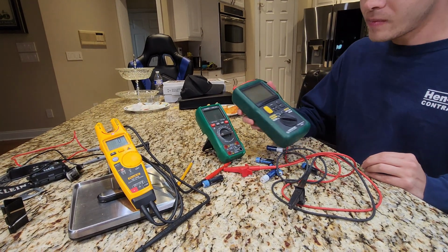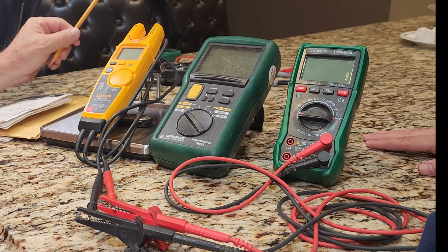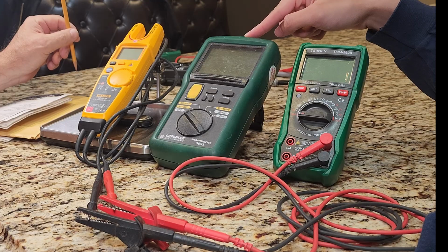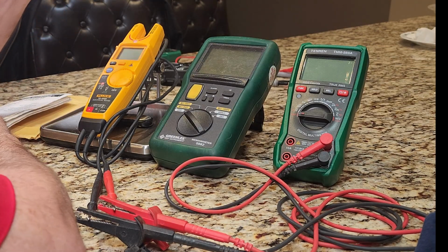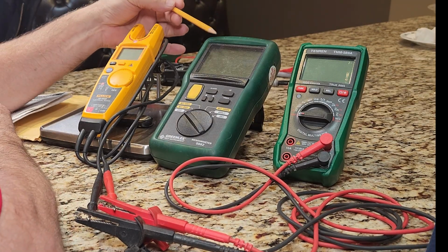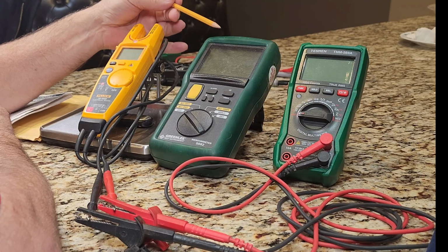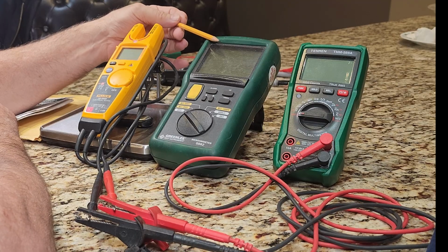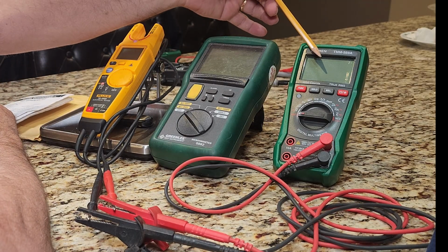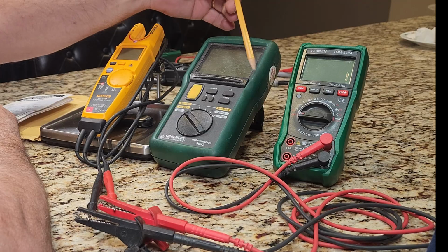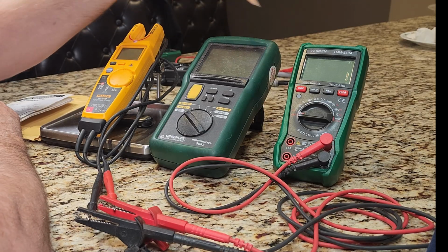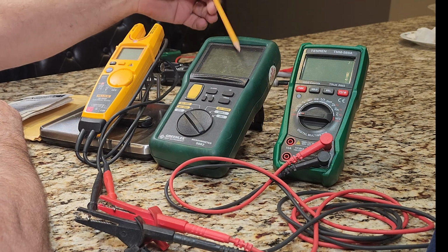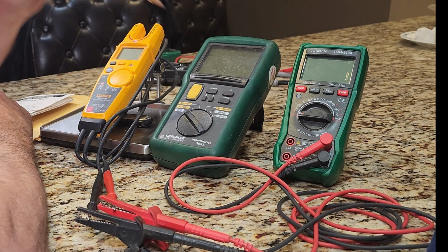All right, let's see. Hey, Dad, what's the difference between resistance and continuity, and why would I need to use this megohmmeter? It's a great question. So, the megohmmeter is much more powerful. It's a specific meter with just one testing parameter, resistance. This is a multimeter that does continuity, AC, volts, and resistance. So I'm going to show you the difference between these two meters and why it's so important to have a megohmmeter in certain applications and when you would use it.